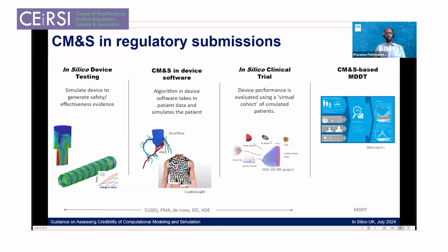So these first three cases are all about single devices. We also have something called MDDTs, which are medical device development tools. These are tools that organizations, not necessarily device developers, but any kind of organization, can submit to FDA, to CDRH, the Devices Center, a tool that they claim is going to be useful for the medical device industry to evaluate their devices.